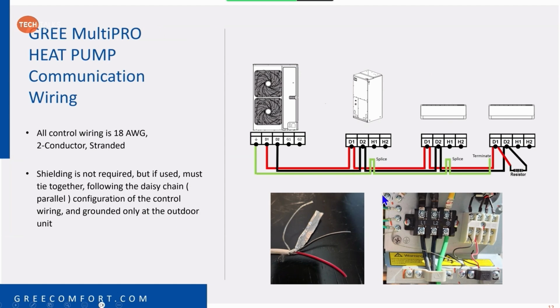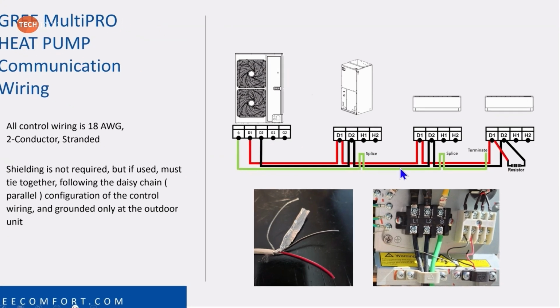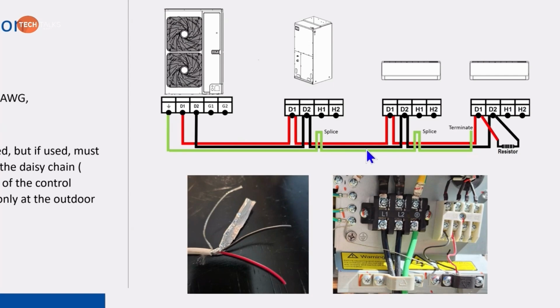So, the grounded shield. The reason you don't put grounds on both ends is because then it becomes a ground conductor, and it'll actually conduct. If you get electrical interference, it doesn't have one direct path. The whole idea with grounded shielded is that any interference, whether it be from a fluorescent light, from another inductive load, whatever it is, trying to interfere with that comm line hits that ground wire, has one path to ground, and gets rid of it. When you have more than one path to ground, it just stays on the wire, kind of bouncing back and forth, and it doesn't really get rid of your interference.